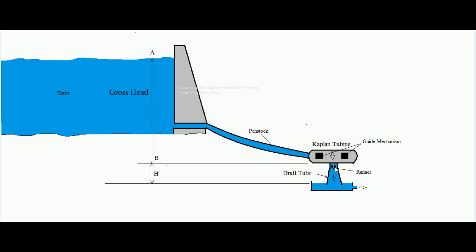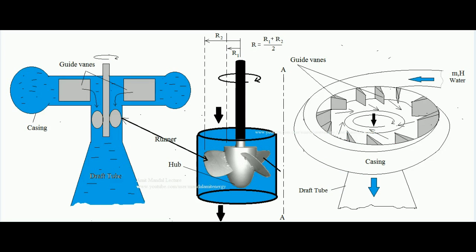One thing we can learn here is that the Kaplan turbine is a reaction type of turbine. Reaction means it runs on the pressure energy of water — the pressure falling over the blade of the runner drives it to rotate in a corresponding direction, and this is how power is developed. Second, it is an axial flow machine, meaning the flow of water through the runner is along the axis of the runner.